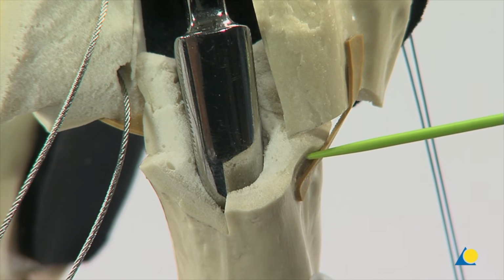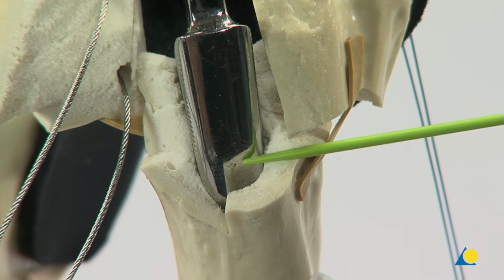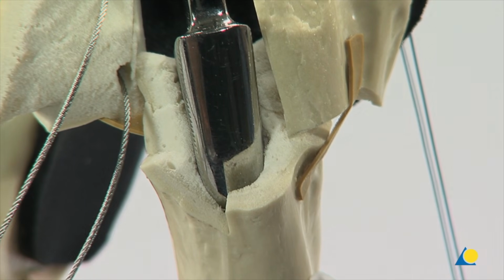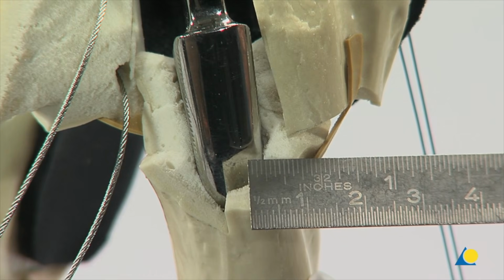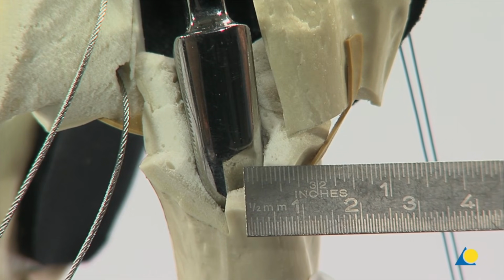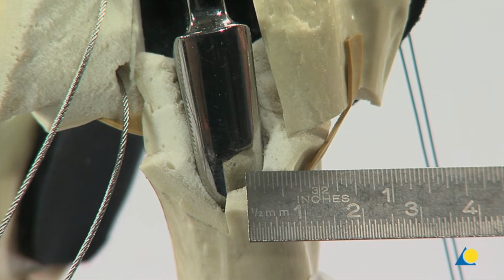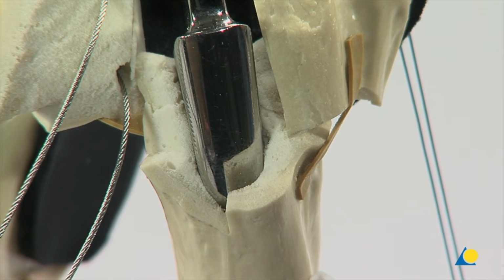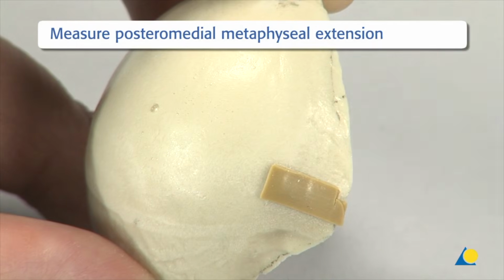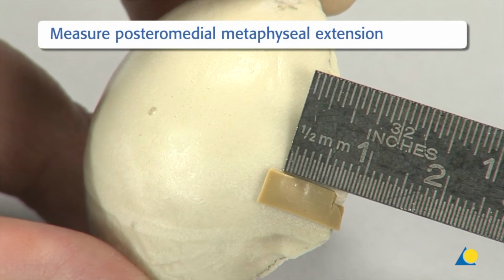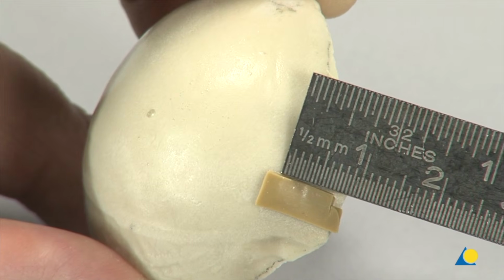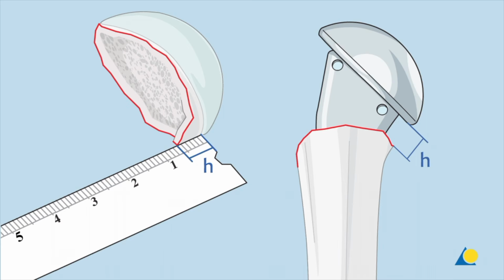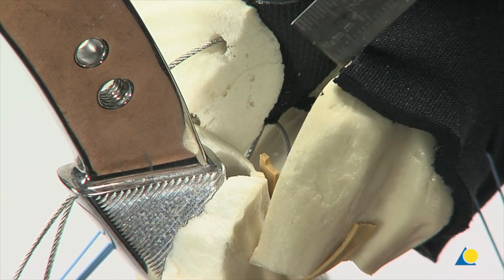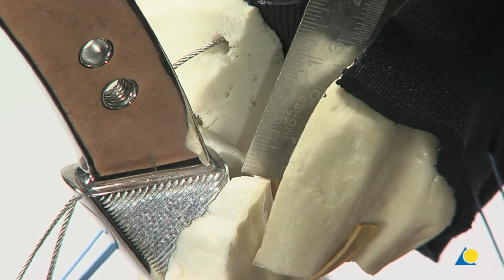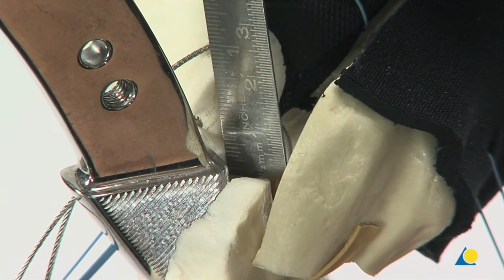The retrotorsion is confirmed by cross-checking against the bicipital groove. The distance between the deepest point in the bicipital groove and the center of the rasp should be approximately 8 mm. The posteromedial metaphyseal extension H is measured on the retrieved humeral head and noted. This distance determines how much the stem must protrude above the medial fracture line. The rasp is hammered in until the correct prosthetic height H, as measured previously, is obtained.